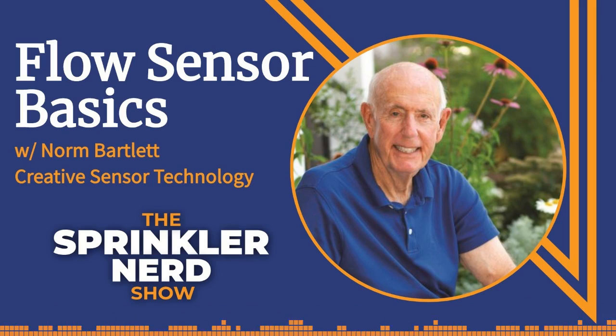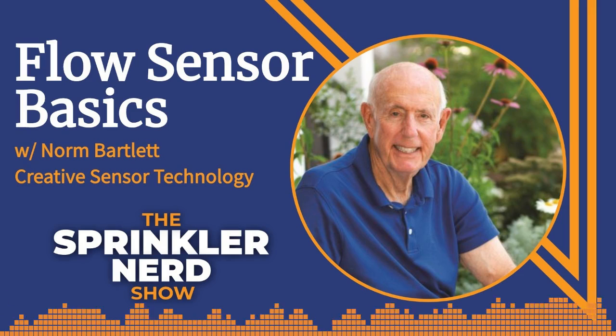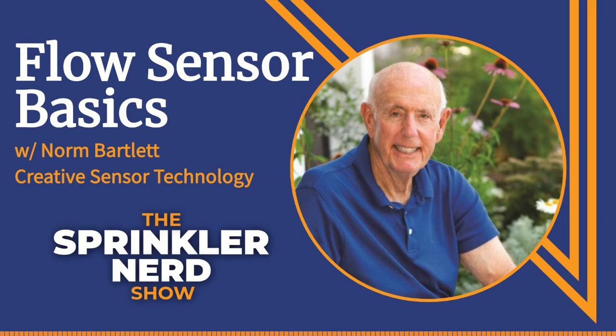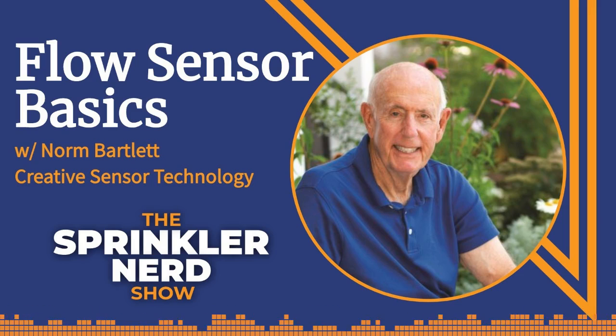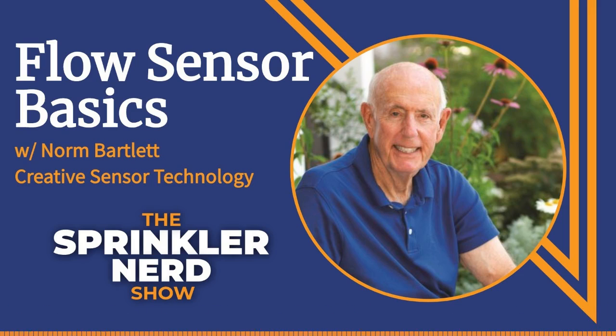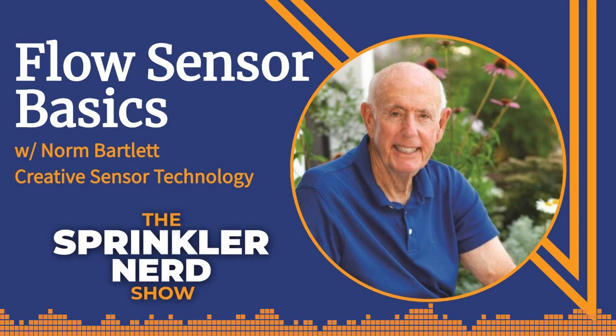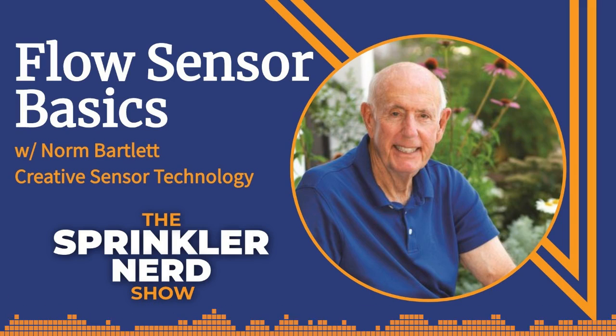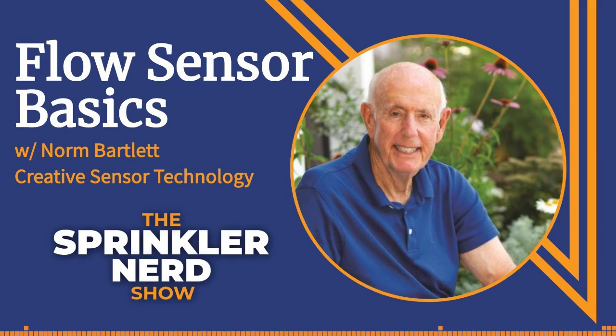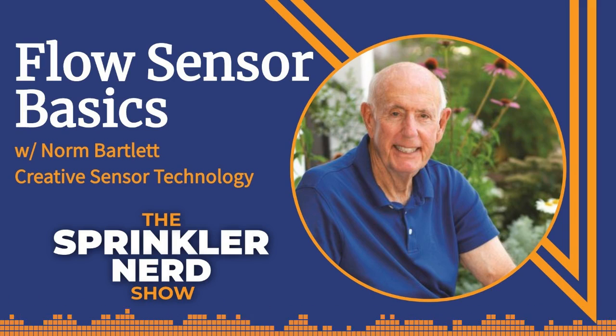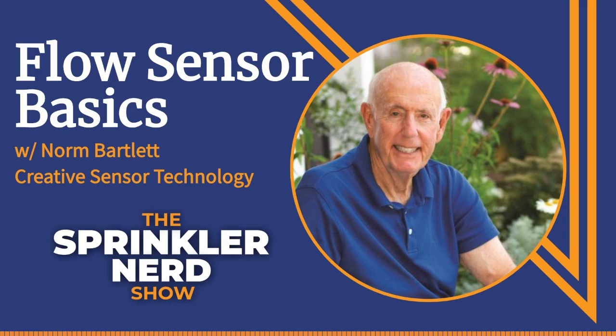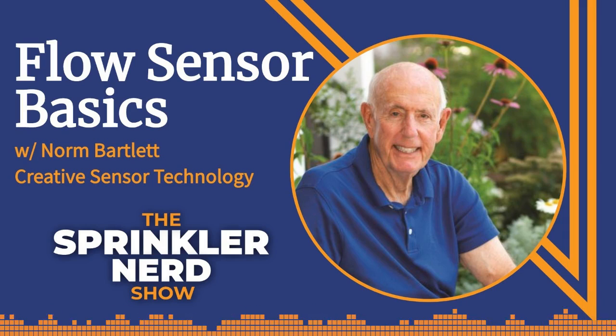The other thing with the wiring, one of the things that we find the most problematic is splicing. Flow sensors are probably even more affected by poor splices than solenoid valves are, because they're data communication. They're not just electrical power to open a solenoid or turn on a light. They're actually transmitting data, and it's also a DC voltage. Okay, interesting. That's a good point. So it's more critical.